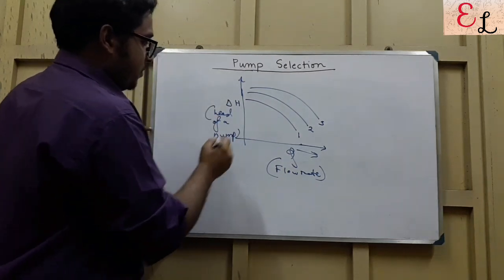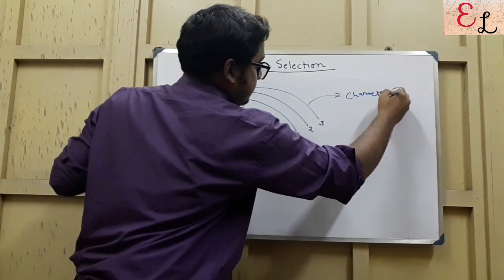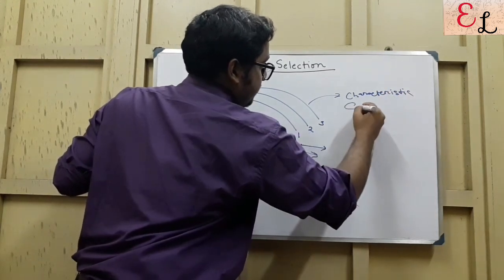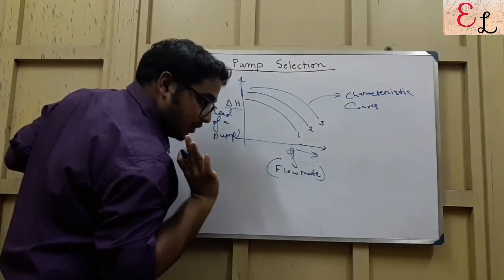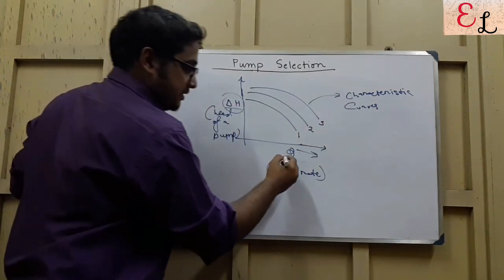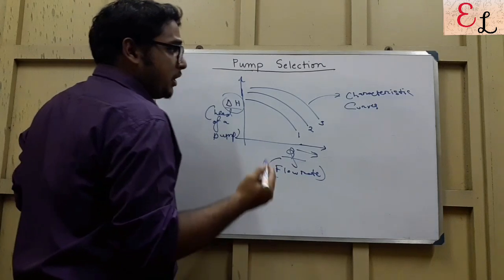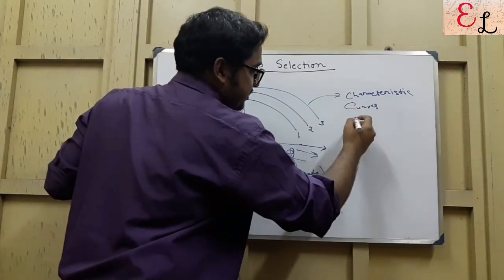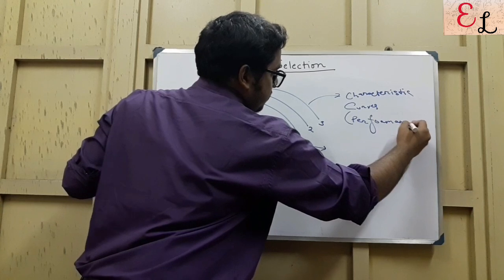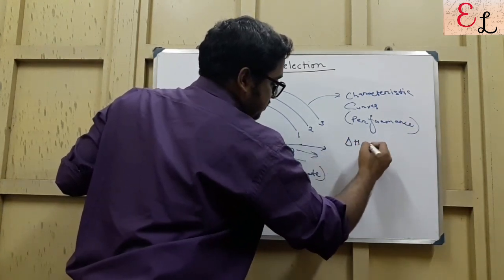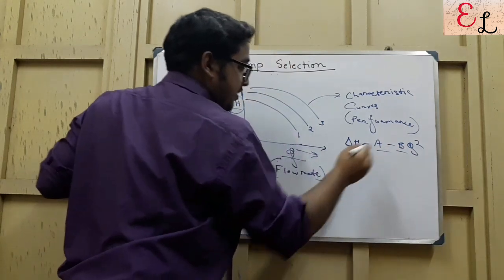How does this relationship come from? These are called the characteristic curves. What does this signify? It is the head developed by a pump, the discharge head developed by the pump, given by delta H and how it varies at different flow rates. So this is the characteristic curve, also known as the performance curve. The performance curve has a relation of delta H equals A minus B Q square.